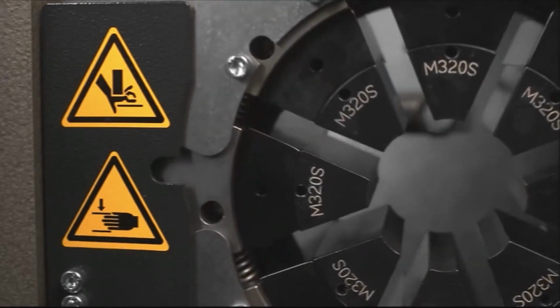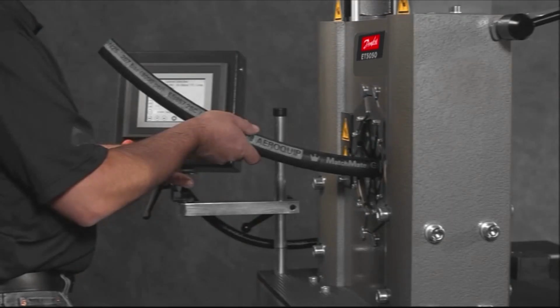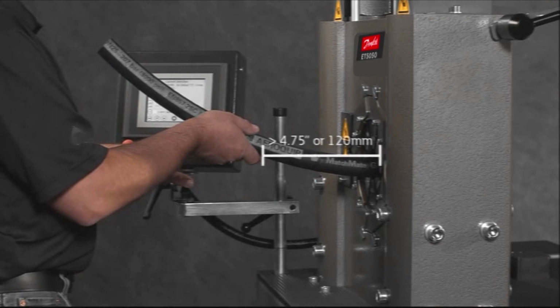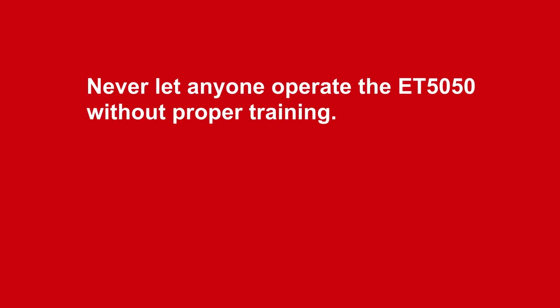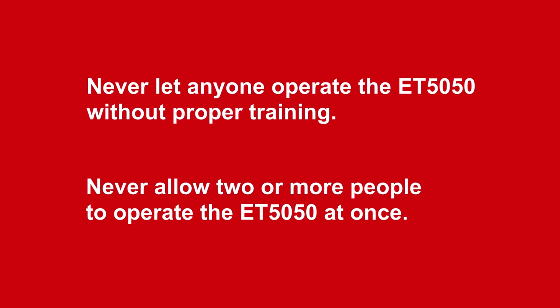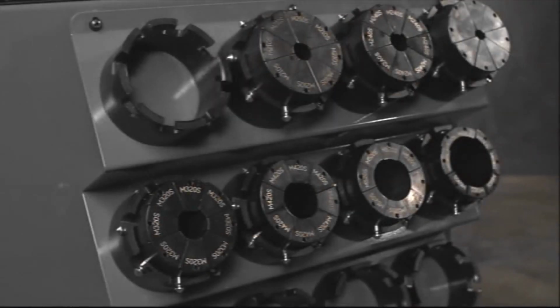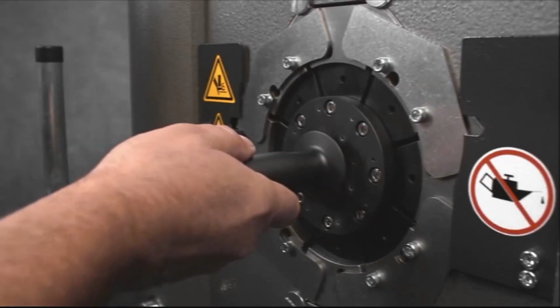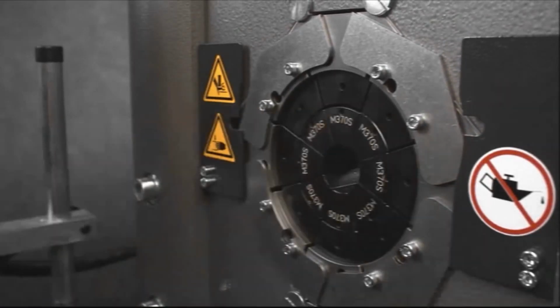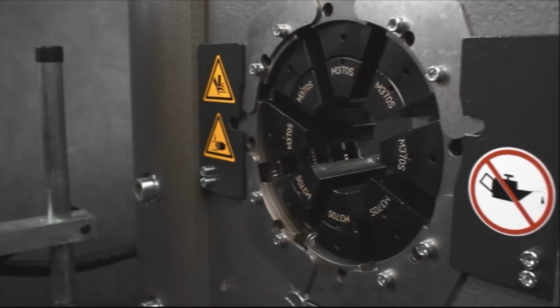During the crimp operation, always ensure that your hands are at an adequate safety distance of 4.75 inches or 120 millimeters from the crimping tool and clear of all moving parts at all times. Never let anyone operate the ET5050 that has not been properly trained or read the operator's manual. Never allow 2 or more people to operate the machine at the same time. Use care when handling the dies and use only the Danfoss approved quick die change tool, referred to as the QDC tool, to install or replace dies.